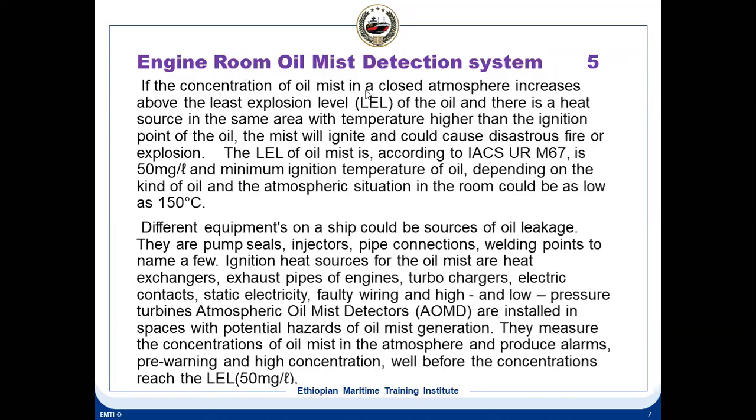Engine room oil mist detection system. If the concentration of the oil mist in the closed atmosphere increases above the LEL level of the oil. You see, you have lube oil pumps, main lube oil pumps. Let's take one example of main lube oil pumps. Suppose there is an oil leakage in a UMS ship. This oil mist can cause a fire explosion, a fire hazard. So to detect any leakage of lube oils or any oils, we have the oil mist detection systems in the engine room.